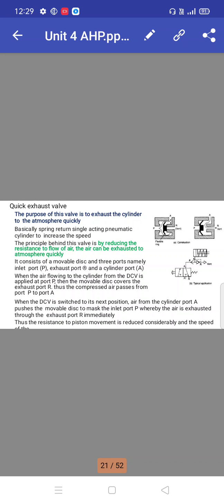It consists of a movable disc and three ports: inlet port, exhaust port, and cylinder port. When air flowing to the cylinder from the DCV is applied at port P, the movable disc covers the exhaust port. Thus, the compressed air passes from port P to port A.